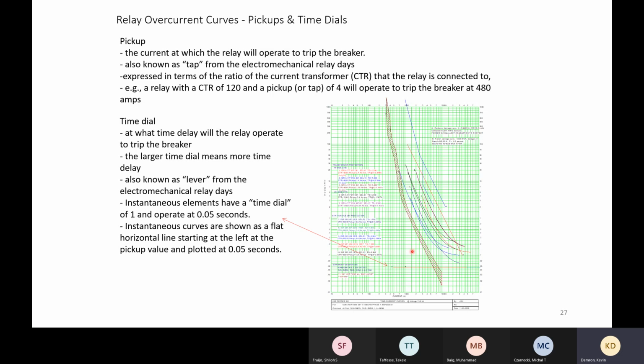Our philosophy is, and different utilities have different practices, we do one fast and one slow reclose. So the first operation is by our 50 elements. We'll trip. Again, we're trying to save this fuse, make sure that we don't have to replace it. So we'll trip, wait half a second, reclose it back in, then we turn these off. At that point, we're just using the 51 elements to coordinate, each one backing up the other. Ideally, we don't get up into the transformer, because that's bad. That means the fuse somehow failed, my substation breaker failed, and now I'm getting up into the transformer protection to back this thing up. So ideally not doing that.